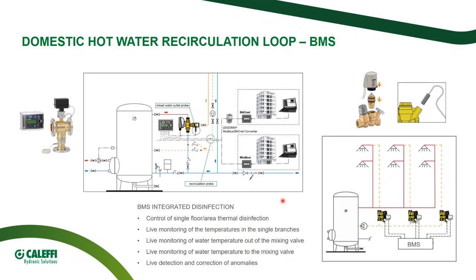Also, this system enables the user to perform the thermal disinfection of the branches and or of the riser separately, so step by step. So maybe the program can be, let's flush riser number 1 today, riser number 2 tomorrow, and riser number 3 the day after tomorrow. It can be done with the BMS integration. So I can control the single floor and area. I have live monitoring of the temperature in each single branch. And also I have live monitoring of the temperature in the thermal room, because if you remember, we have the probes. And I also have live detection and correction in case of any anomaly in the system.